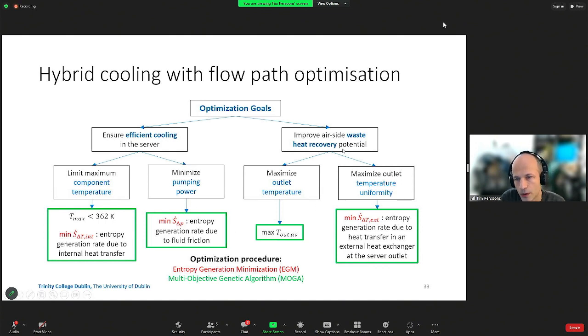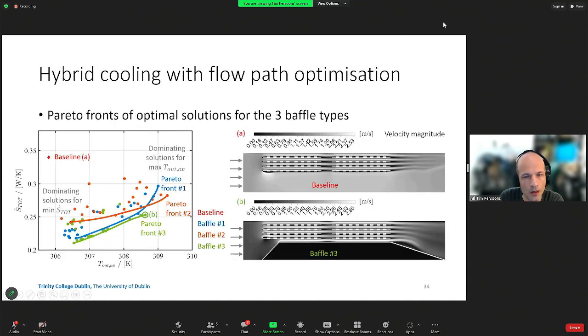But of course, we want to do more, right? We want to enhance the waste heat recovery potential. So we want to maximize the outlet temperature and also its uniformity, so that if that air flows over a heat exchanger, we're more easily able to extract the heat from the system. So it's a combination effectively of EGM, so entropy generation minimization, with a MOGA algorithm. And because of the multiple objective functions, you won't get a single optimal solution, but you'll get a Pareto front, right? You get multiple different potential optimum solutions, depending on what you decide is the dominant objective.